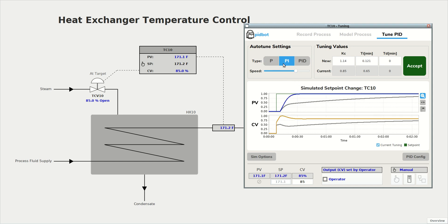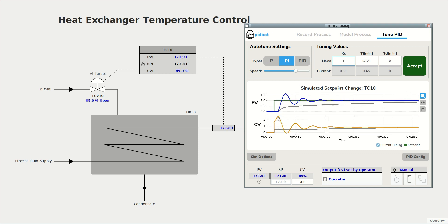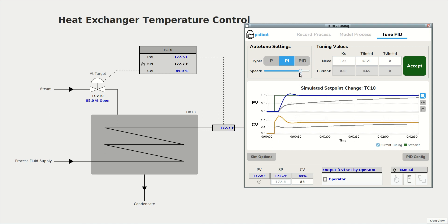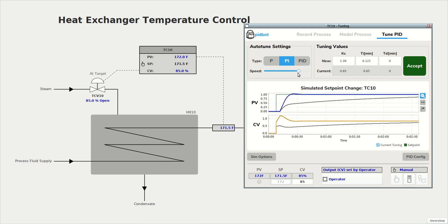In our case, we'll stick with the PI controller. But you could also manually adjust the tuning values. And PIDBOT is going to show you what that response might look like with our model process. But we'll stick with the PIDBOT suggested values. And we'll pick a point with not much overshoot. And we want to make sure that we can tolerate this much control action. And in our case, we can. So this looks great. We're going to accept those values.